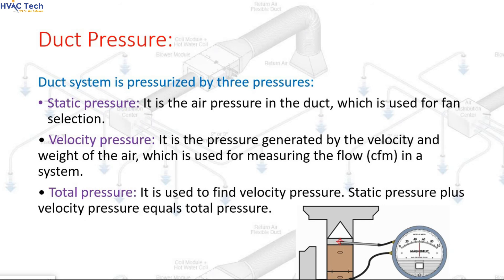Duct pressure: a duct system is pressurized by three pressures. Static pressure is the air pressure in the duct, which is used for fan selection. Velocity pressure is the pressure generated by the velocity and weight of the air, which is used for measuring the flow (CFM) in a system. Total pressure is used to find velocity pressure. Static pressure + velocity pressure = total pressure.